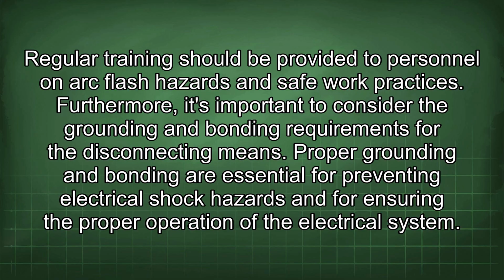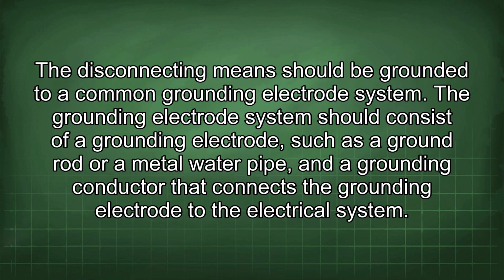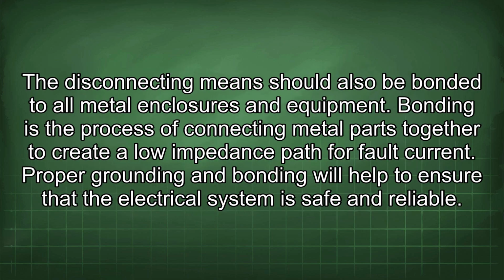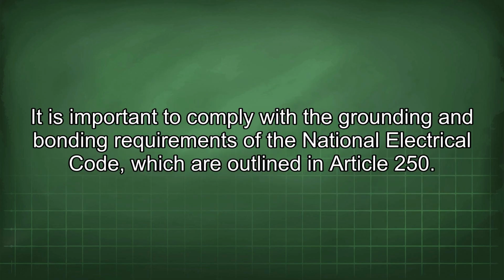Furthermore, it's important to consider the grounding and bonding requirements for the disconnecting means. Proper grounding and bonding are essential for preventing electrical shock hazards and for ensuring the proper operation of the electrical system. The disconnecting means should be grounded to a common grounding electrode system. The grounding electrode system should consist of a grounding electrode, such as a ground rod or a metal water pipe, and a grounding conductor that connects the grounding electrode to the electrical system. The disconnecting means should also be bonded to all metal enclosures and equipment. Bonding is the process of connecting metal parts together to create a low impedance path for fault current. Proper grounding and bonding will help to ensure that the electrical system is safe and reliable. It is important to comply with the grounding and bonding requirements of the National Electrical Code, which are outlined in Article 250.